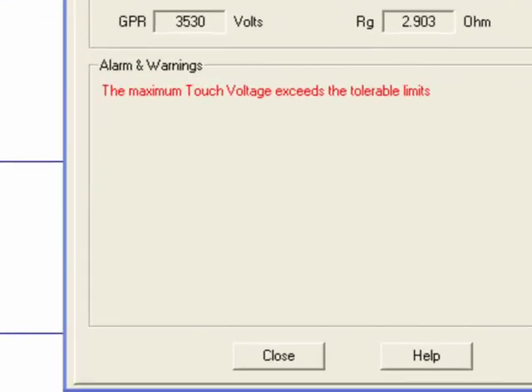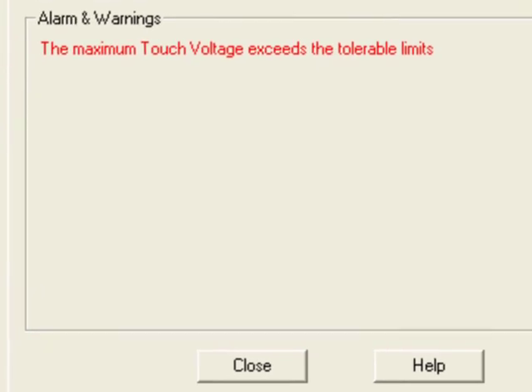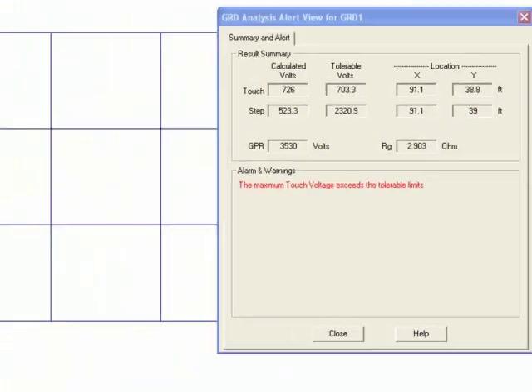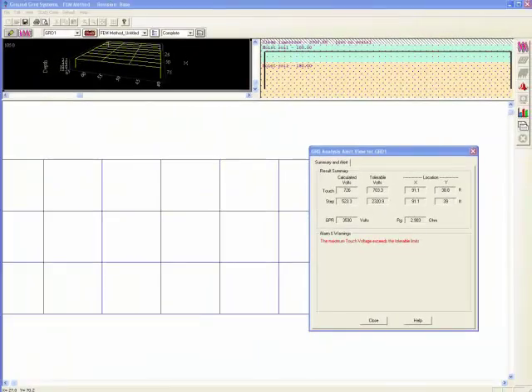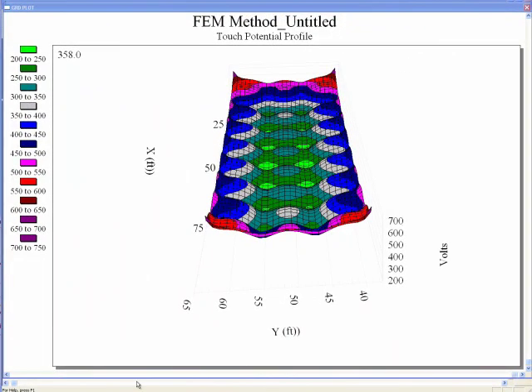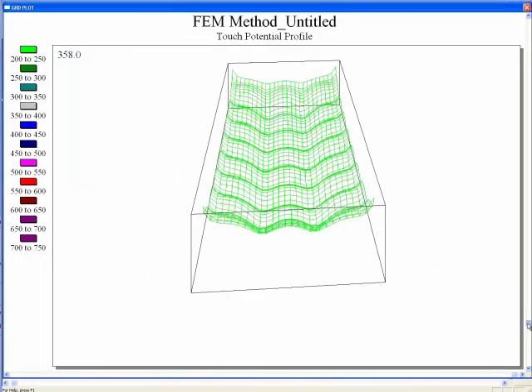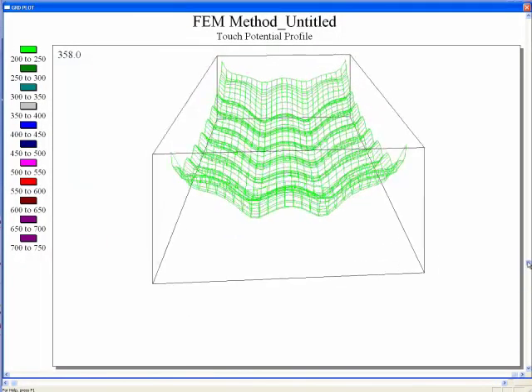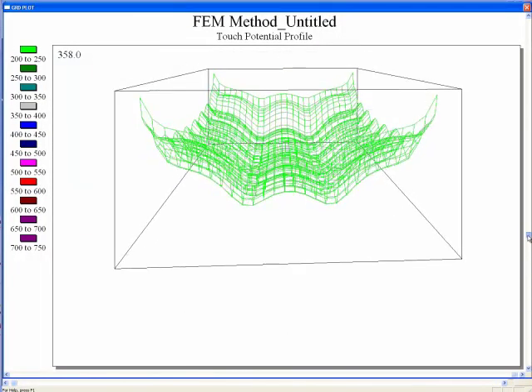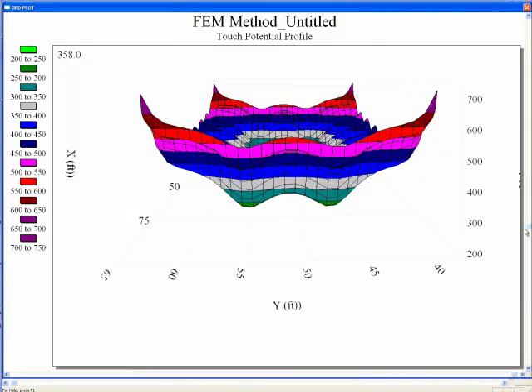As a result of analyzing this specific case, the maximum touch voltage exceeds its tolerable limit. Using the plotting capability in ETAP, the peak touch voltages are clearly observed at the corners of the ground grid system voltage profile.